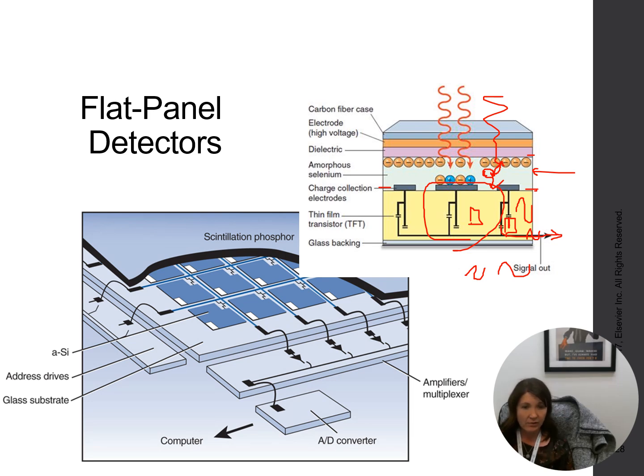Here's an example of just the scintillation phosphor. So if this is scintillating, we know this is an indirect flat panel. It's got the scintillation phosphor. Photon would come in. It would create a light. Light would then be coupled with fiber optics or some other entity like amorphous silicon, and then that sensitive area that is filled with sensitive devices on the TFT would absorb that light, and then the TFT would convert it to electrical signal, and that electrical signal would be stored here in the capacitor until it was time to be read out, in which it would go through the transistor.